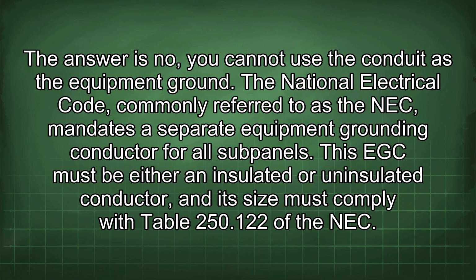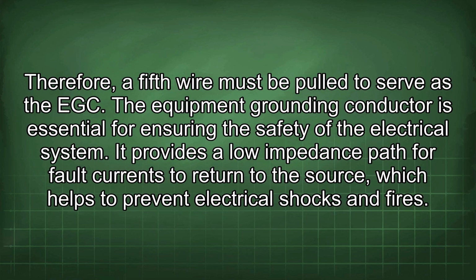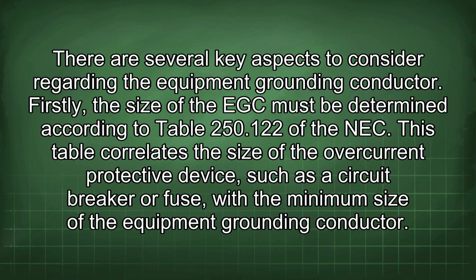The National Electrical Code, commonly referred to as the NEC, mandates a separate equipment grounding conductor for all subpanels. This EGC must be either an insulated or uninsulated conductor, and its size must comply with Table 250.122 of the NEC. Therefore, a fifth wire must be pulled to serve as the EGC. The equipment grounding conductor is essential for ensuring the safety of the electrical system. It provides a low impedance path for fault currents to return to the source, which helps to prevent electrical shocks and fires. There are several key aspects to consider regarding the equipment grounding conductor.